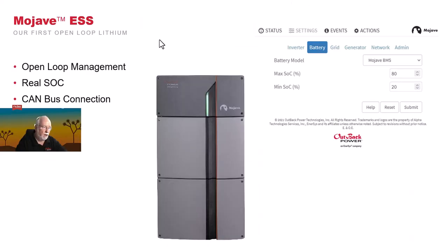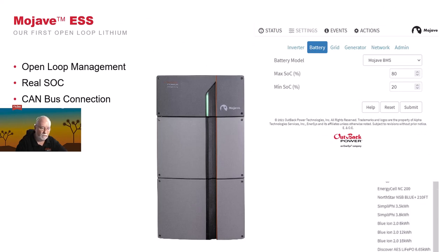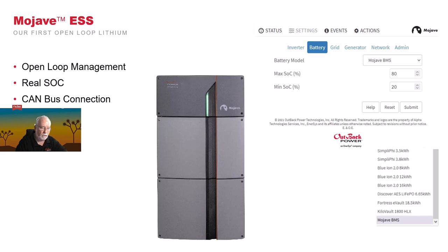Also, on the Mojave battery, it's really simple. You just simply go to the bottom of the dropdown, and select Mojave BMS, hit submit. It'll come up. Normally, when you first plug it in, you don't even have to do this. You simply plug it in. When the unit fires up, if there's no other batteries that have ever been defined, it will default to this battery. The only things you set on this are your max SOC and min SOC. Click submit. If you change to a different battery, or if you selected the wrong battery and had to go back to the ESS, when you do, these values might be 100 and 0. Just set them according to what you need.